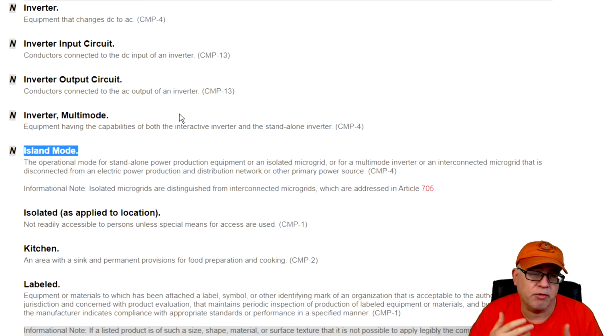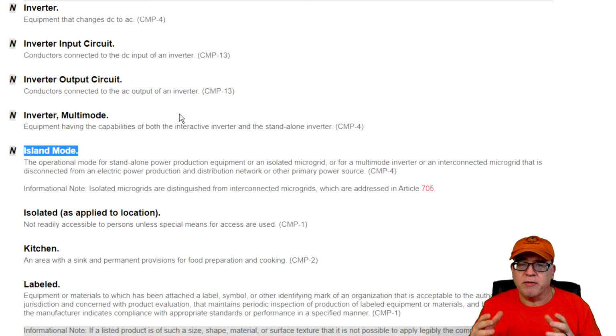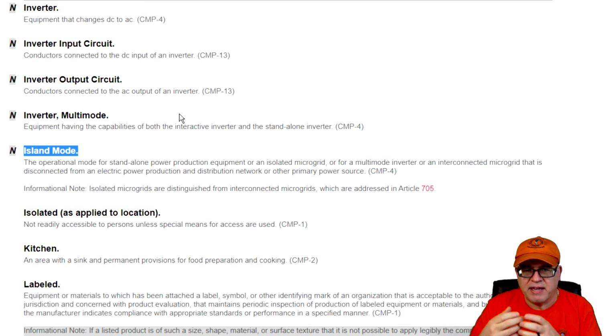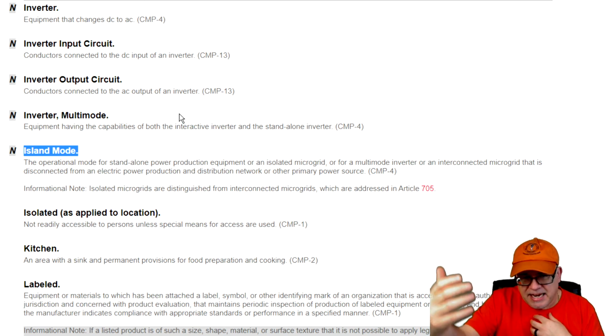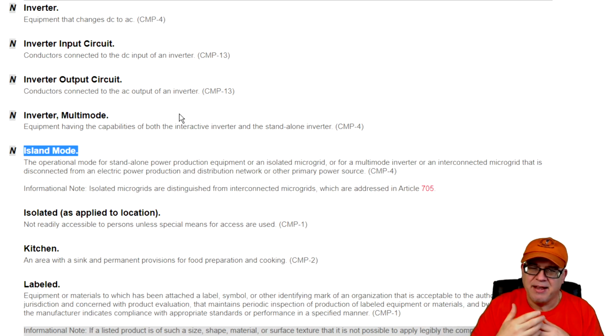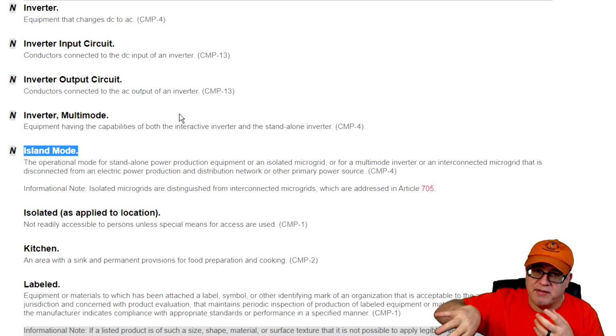So if you ever wondered the difference between an inverter and a converter, just remember a converter plugs into the wall, right? So it's got to take AC and make it DC. An inverter is the opposite. It's taking DC, turning it to AC. So inverter, converter, just so you know the difference. What is inverter input circuit? It's the conductors connected to the DC input of an inverter. So if I have an inverter that's for like a PV system, it's the conductors connected to the DC input of the inverter. So you're coming in from the DC source into the inverter, it's still DC, and it's going to go into the inverter because ultimately it's coming out of the inverter as AC current so that we can use it, right?